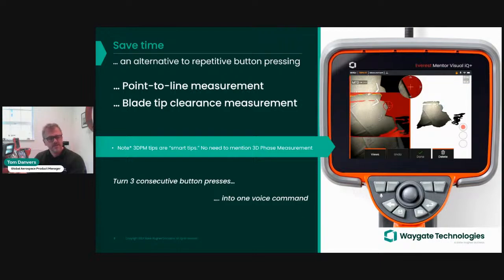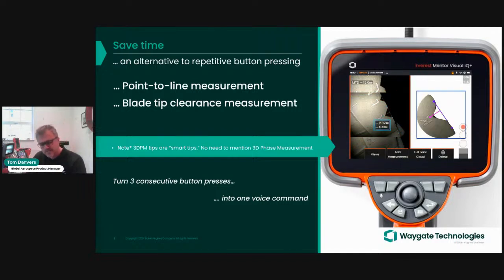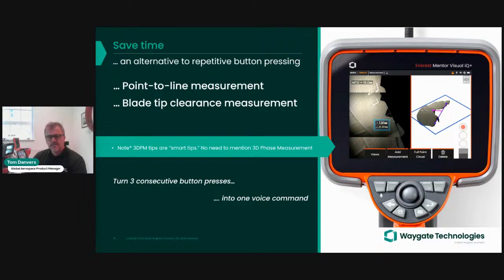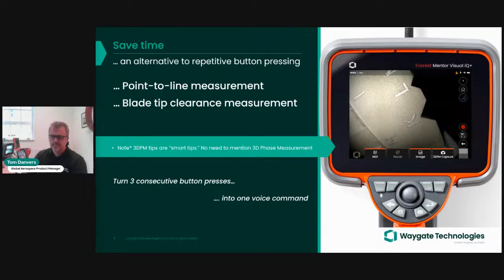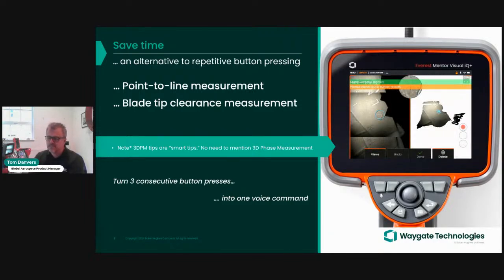So this is relevant for when you've got a 3D phase measurement tip fitted, because 3D PM tips are smart tips. As you attach and detach them from the probe, the device understands what tip that is, and what serial number it is, and all that calibration data is appropriately loaded in such that when you take measurements, they're accurate measurements. So there's no need to say "3D PM capture." You can say that, but you can just say "point-to-line measurement." And because your 3D PM tip is already fitted, it will do a 3D PM capture and then automatically select the point-to-line measurement, for example, if that's what you commanded.